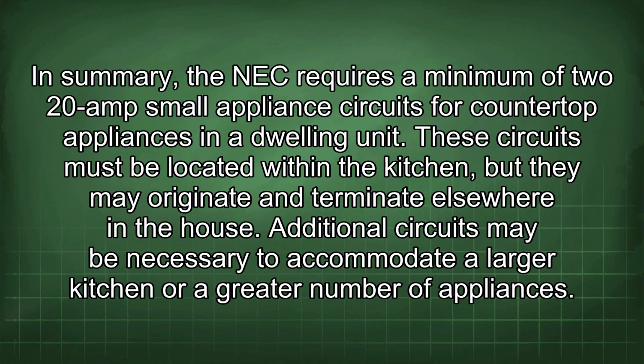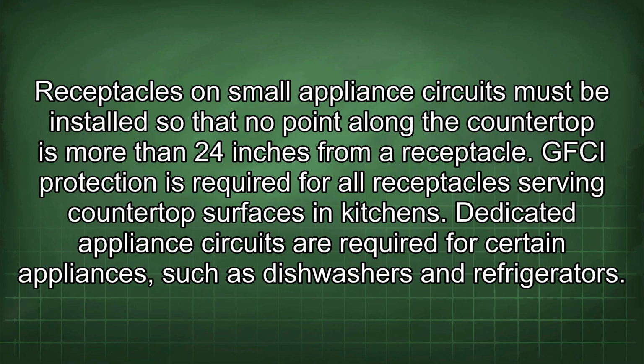In summary, the NEC requires a minimum of two 20-amp small appliance circuits for countertop appliances in a dwelling unit. These circuits must be located within the kitchen, but they may originate and terminate elsewhere in the house. Additional circuits may be necessary to accommodate a larger kitchen or a greater number of appliances. Receptacles on small appliance circuits must be installed so that no point along the countertop is more than 24 inches from a receptacle. GFCI protection is required for all receptacles serving countertop surfaces in kitchens.